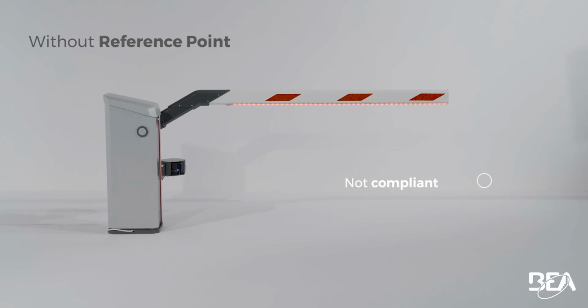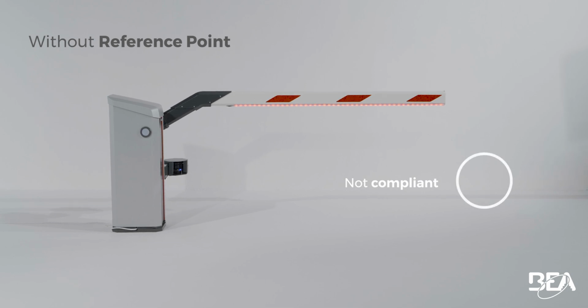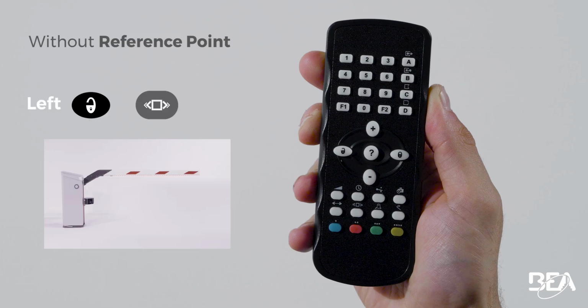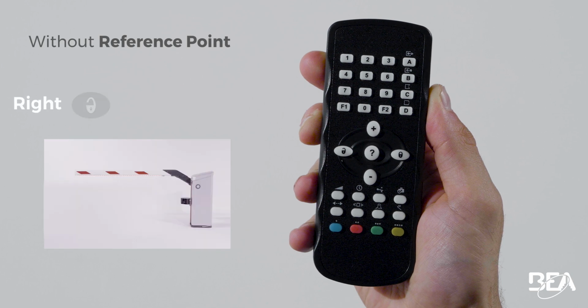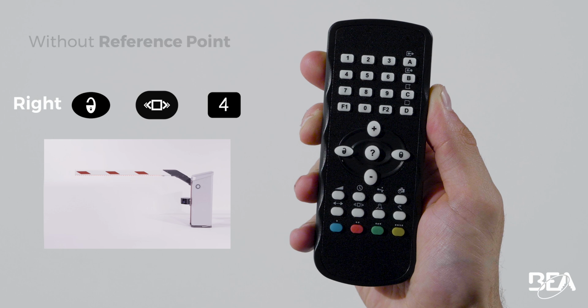You can also select a mounting side without reference point. Be aware that a complementary safety device might be needed to meet safety regulations. For a mounting on the left side without reference point, select value 3. For a mounting on the right side, select value 4.